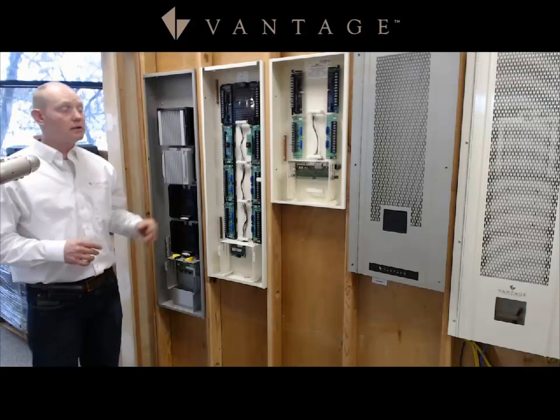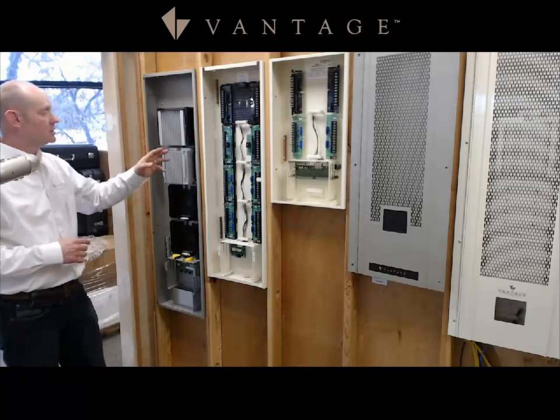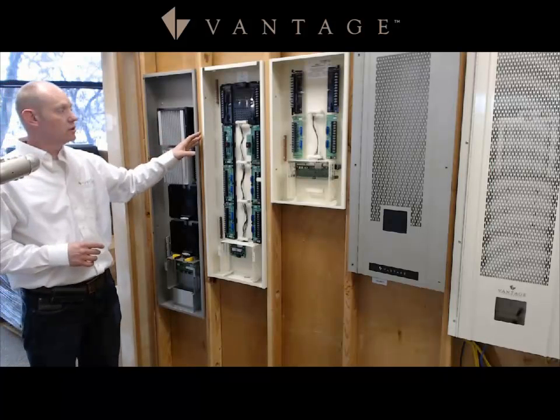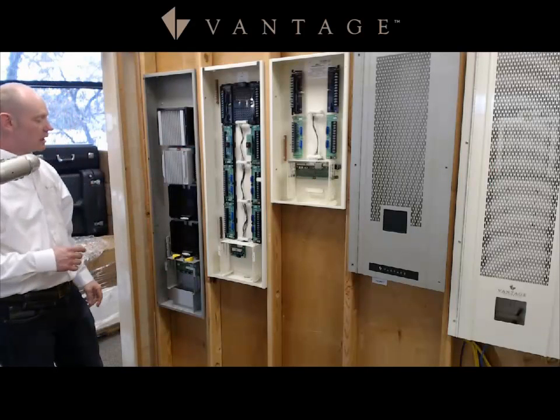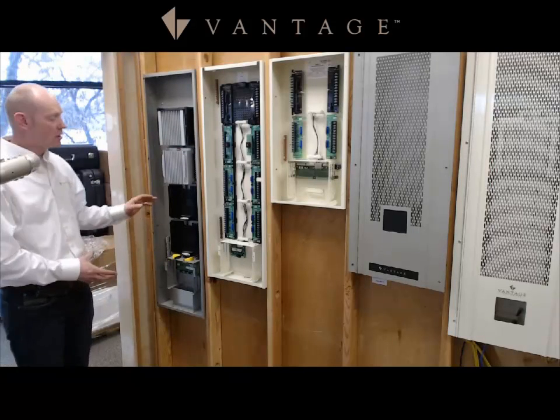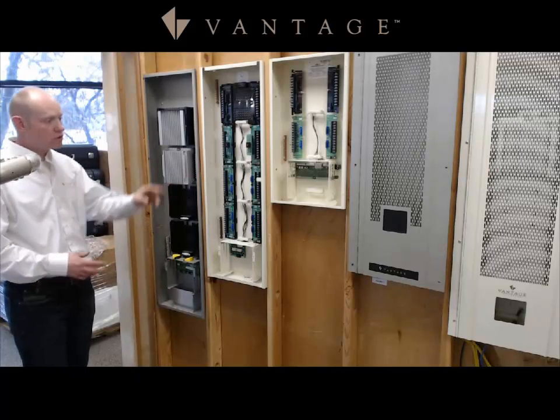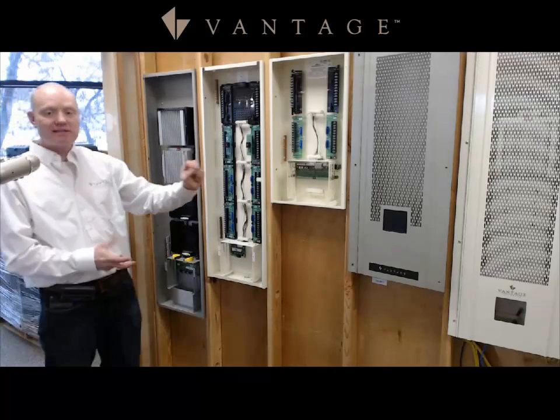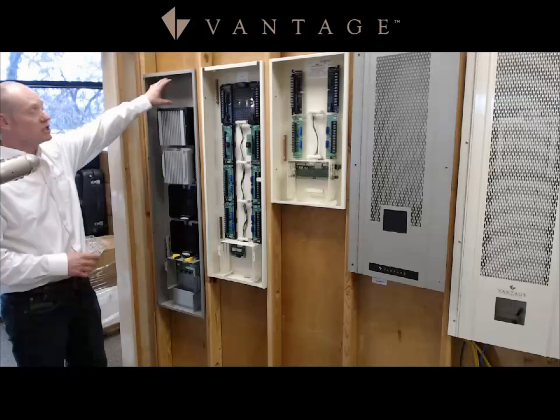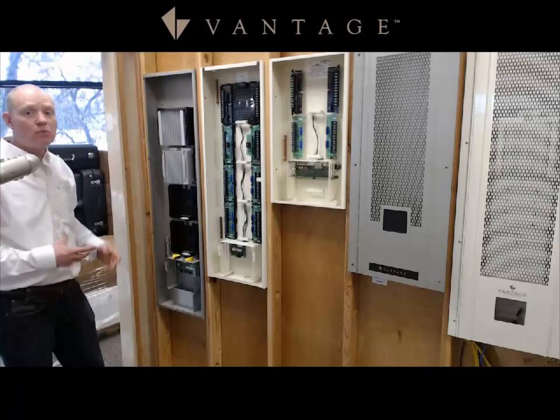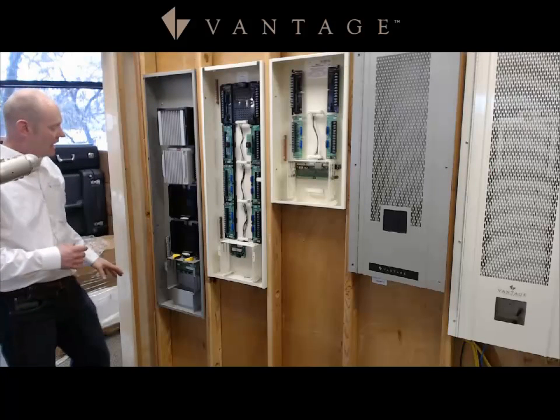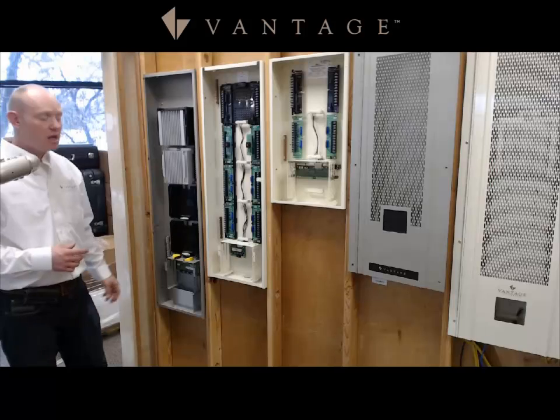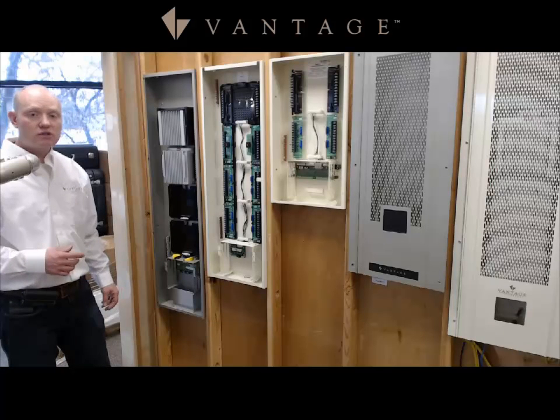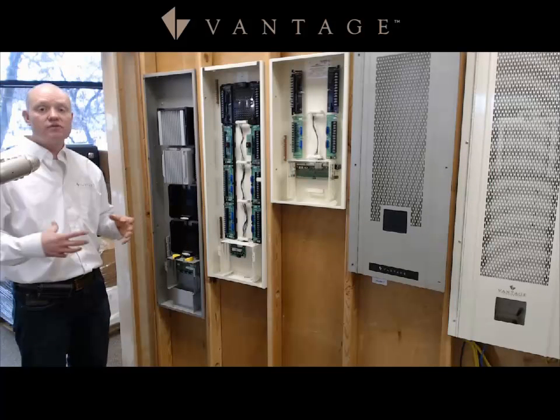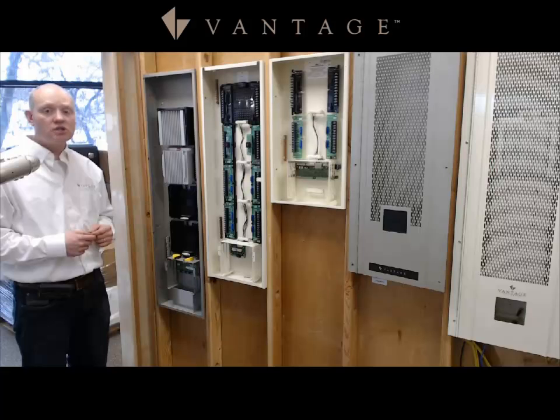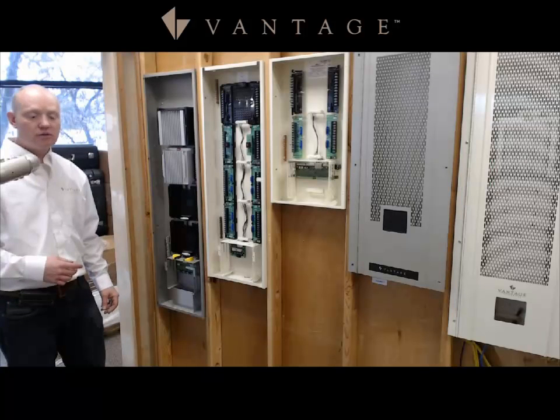So we're looking at the new enclosure modules next to the old enclosures. As you can see right from a glance, they are about 10 inches larger than the old 4 module enclosure, and the same with the 2 module enclosure, about 10 inches. What we've given you is additional headroom because we've got about 50% more loads coming into this enclosure, as well as the low voltage cage down below, which allows you to make up all those different home runs of station bus underneath in there.